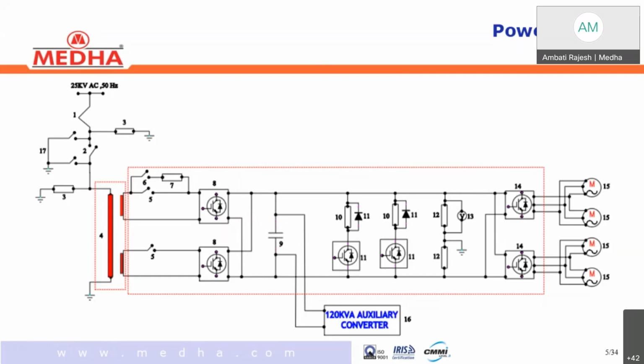And here further, these are the brake chopper circuits. Brake chopper circuits are for over voltage protection, to provide safety from over voltages. Generally, the DC link should be 1800 volts for normal operation. If, because of any abnormality, this voltage shoots up and touches the set value, which is 2100 volts, the system triggers both of these IGBTs so that these brake chopper resistors act as additional load on the DC link. Because of that additional load, the over and above voltage is choked. Whenever the DC link comes back to the normal operating range, both brake chopper circuits are disconnected from the DC link. So the brake chopper is for over voltage protection.